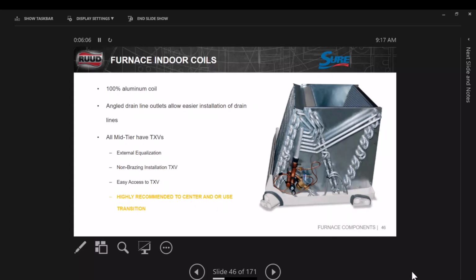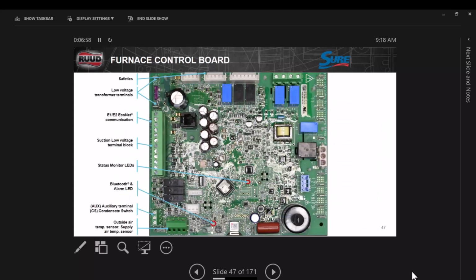All the mid-tier stuff have thermal expansion valves on them with external equalization. We don't have to braze the valve in. It's actually the bolt-in type. It's a mechanical fitting, easily accessible because we put it in here. It's not tucked behind all the tubes and everything in there. We put it up front so you can get to it. And again, we highly recommend using either the center position of the furnace or use a transition, right? We want you to use a transition. You'll get better airflow out of the system and better control of the superheat on the coil.